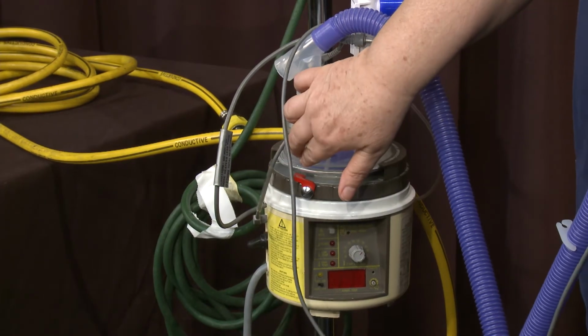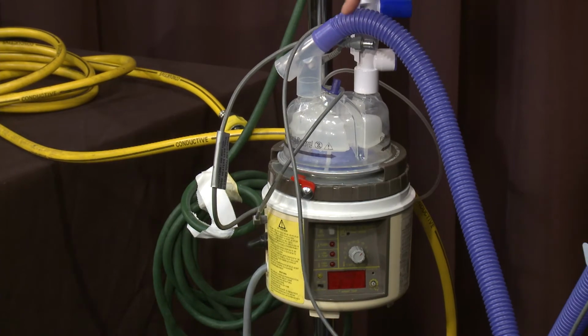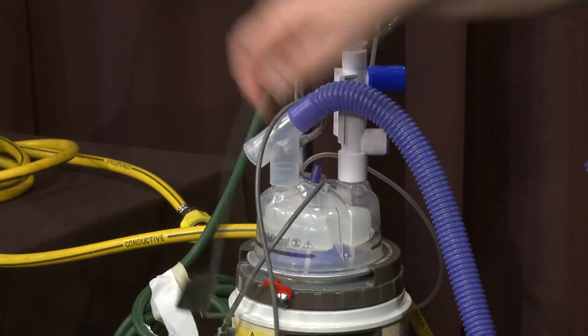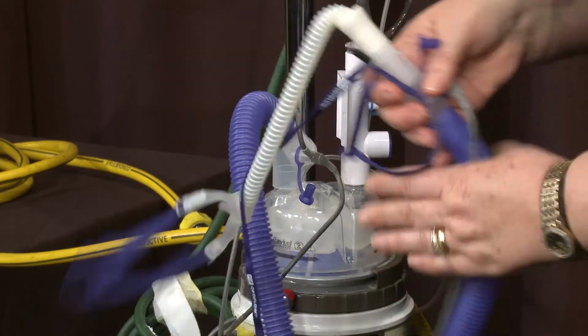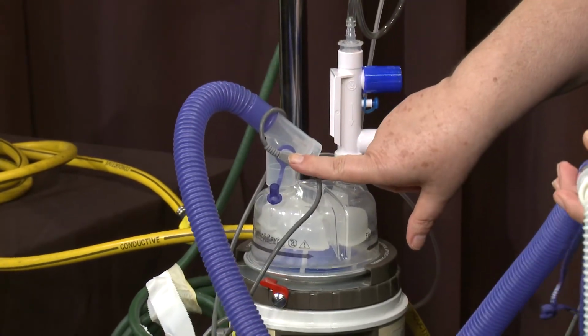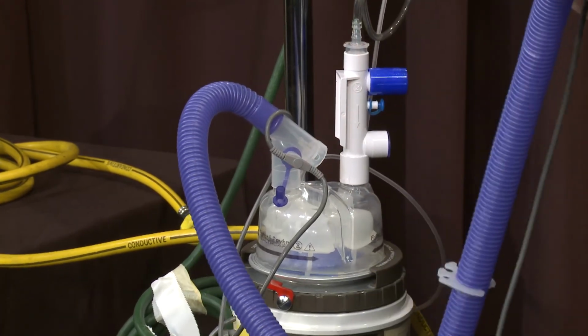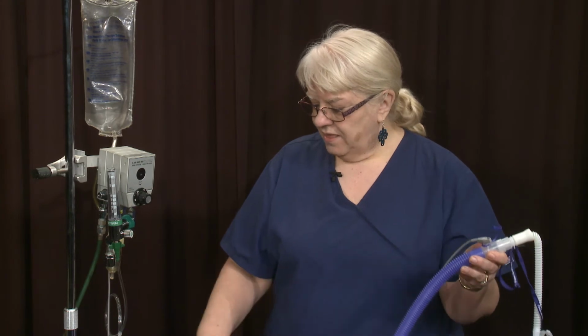The complex humidifier is designed to produce 100% body humidity, in other words, 100% humidity at 37 degrees. Once the gas has been humidified, it then goes out here onto my inspiratory line. Now at this place we have several devices which are designed to help the high flow nasal cannula be efficient. The first device is, let me turn this, right here. This is the proximal probe of the servo loop, and here is the distal probe. This is a feedback loop that constantly adjusts the temperature so we can get it as close to body humidity at 37 degrees centigrade as possible.